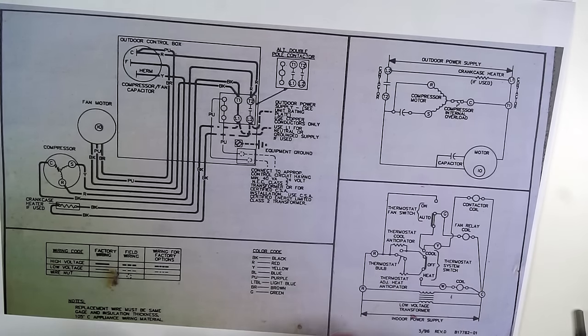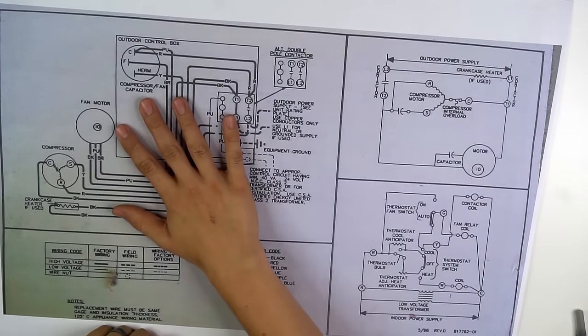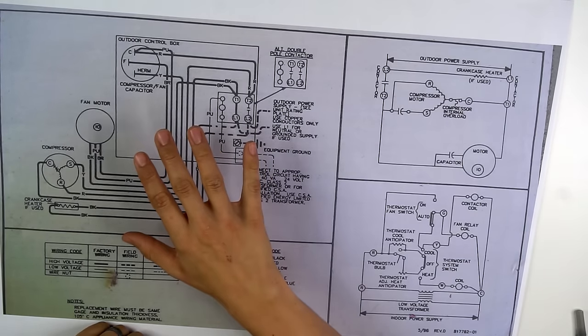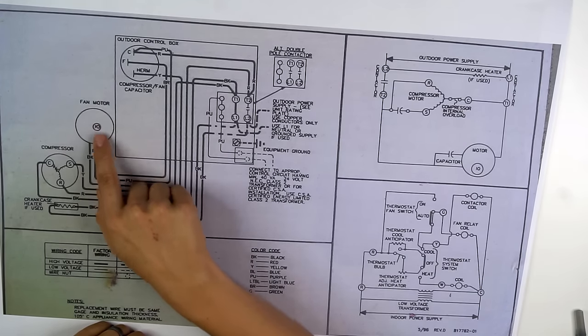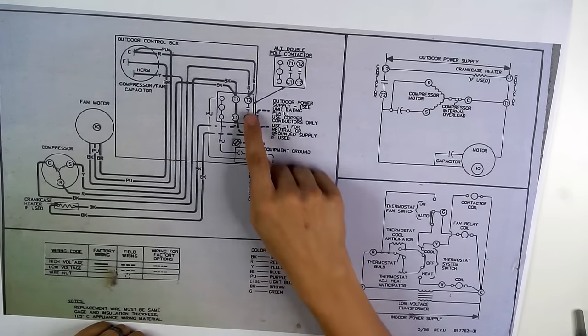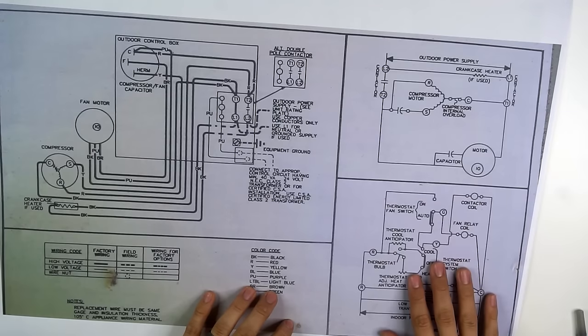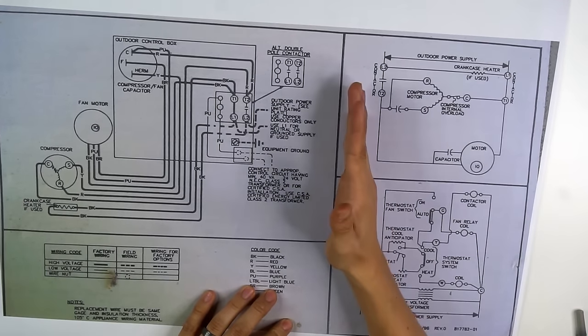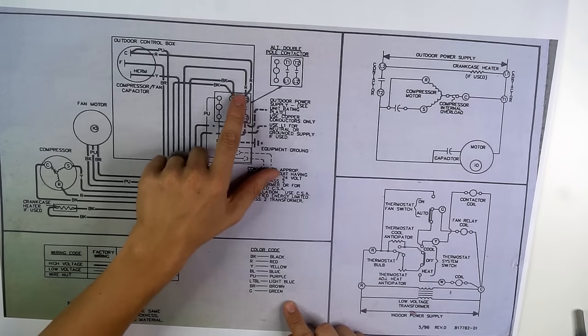On most wiring diagrams you're going to have two sides. On the left side you have the connection diagram, or point-to-point diagram — its purpose is to show which color wires go to which components, with all components in one place. On the other side we have the ladder diagram, which is used more for troubleshooting. It's read from top to bottom, left to right, and the components are not necessarily in the same place as on the point-to-point schematic.